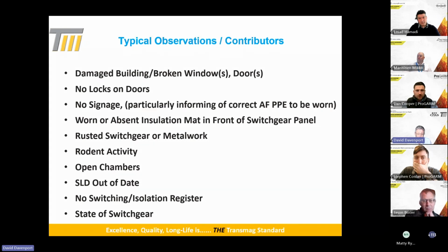Often I see worn or even absent insulation mat, and it could be argued that a worn or turned-up insulation mat is even more of a hazard than not having a mat there at all. You often see rusted switchgear and metalwork, rodent activity, open chambers. How many times do you go into a switch room and see somebody's left one of the covers open? SLDs out of date—it's more rare to find a single line diagram drawing that's in date than one that's out of date. And of course, no switching and isolation register.